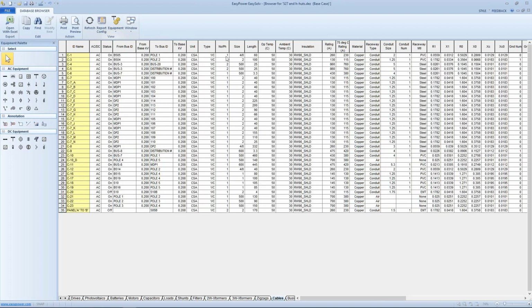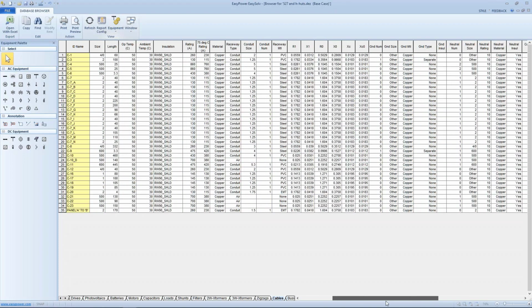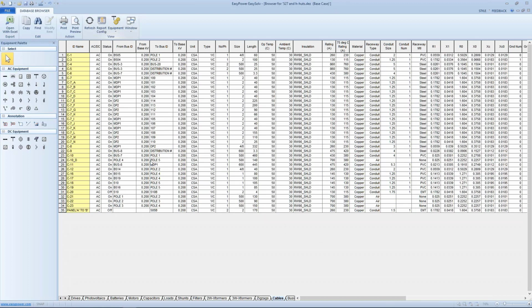Cables is another one to look at. And here, it may not be possible to tell at this level if there's a problem, other than recognizing commonality between, say, cables that we know are grouped together on certain voltage levels, and whether or not they show similar values. If they're different, it could be that we didn't use the calculate button when we entered a different length for that particular cable. Now, to that end, I'll come back to that in a second. All right, so that's cables.